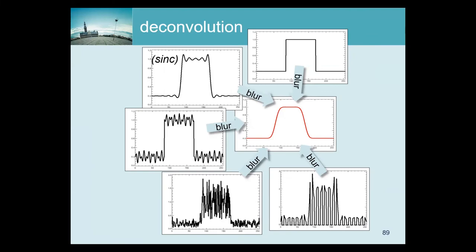And fortunately, in a way, MLEM prefers always to use this solution. It is fortunate because if MLEM would also include stuff like that, we would be very unhappy and we would no longer claim that the noise doesn't propagate. The only reason that the noise doesn't propagate is that MLEM refuses to reconstruct anything that has not been seen. So there is a lot of noise that it cannot explain because if it would put a hot spot in the image to explain the noise, then that hot spot would project as a blob. So that means it can only explain lower frequencies from the noise, but it has no way to explain high frequencies. So all the frequencies that are basically killed by the blurring, they will not be reconstructed and that eliminates a lot of noise.